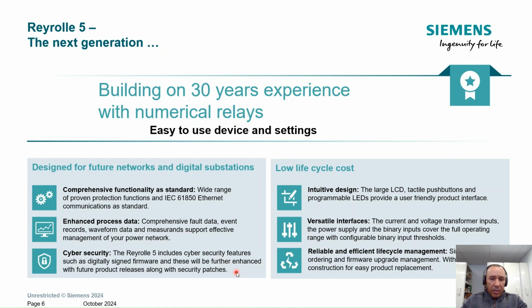Cybersecurity. This device complies with the latest standard on cybersecurity. Intuitive design. This device is very simple to configure, and it brings all the comprehensive protection functions, but the configuration of the device is very simple. Versatile interface. This device has a universal power supply from 24 VDC to 250, also 1 amp and 5 amp CT inputs, and for all the inputs you can select the voltage threshold via software.